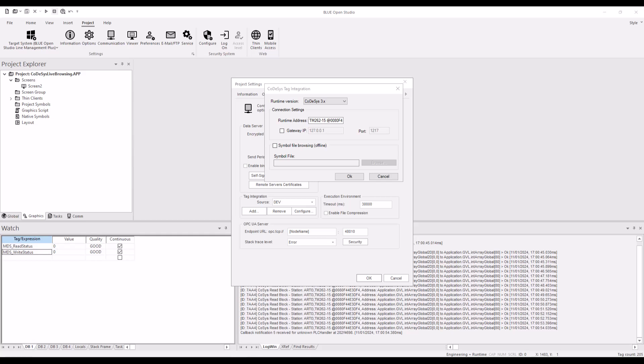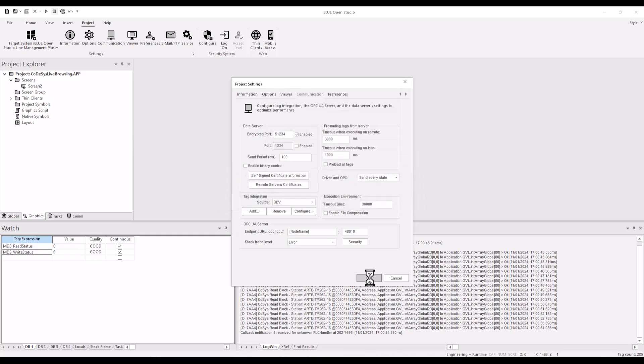We're going to start here in our Blue Open Studio environment and go right into the tag integration settings. What you'll notice is I've got my CODESYS version 3 and then I've got my runtime address. You'll notice that I have not linked up any XML file in this particular project - I'm just using live browsing. I'll click OK and it'll tell me about the refreshing. Right now I do have a good connection and I'm connected to a working PLC; my Blue Open Studio project and my PLC project are in sync.